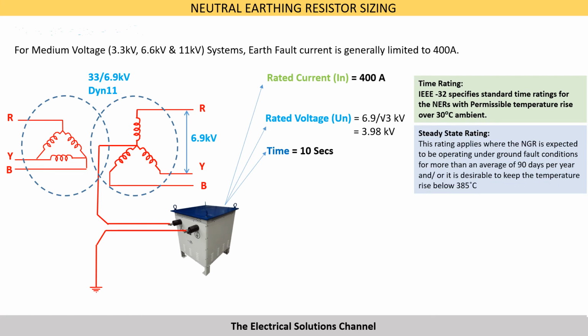The steady state time rating of an NER is applied where the NER is expected to be operating under ground fault conditions for more than an average of 90 days per year, and it is desirable to keep the temperature rise below 385 degrees C.